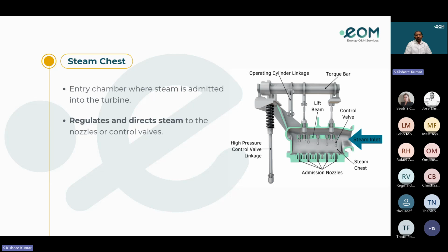In continuous operation of turbines, the ESV is also present. An ESV partial stroke test needs to be performed to avoid choking or jamming of the pistons. In some turbines, if the load is not achieved at more than 100% load, we have to check whether the fifth cone is lifting or not. Based on that, we have to adjust the lift on the side. So it is essential and we have to look after it.